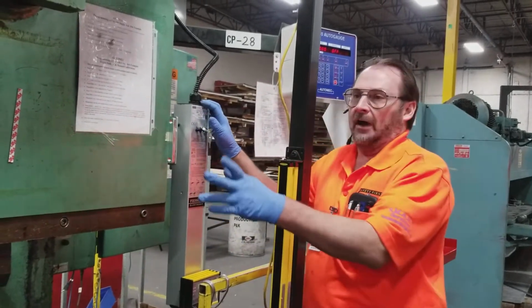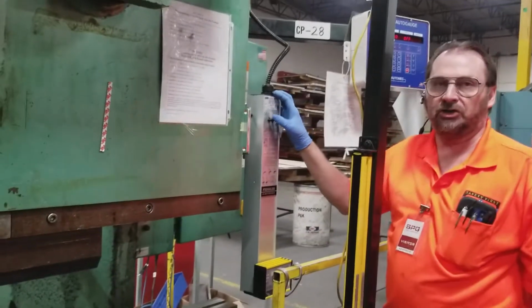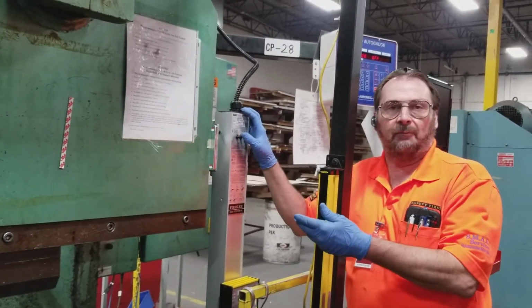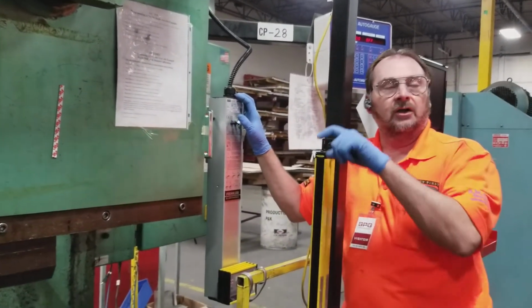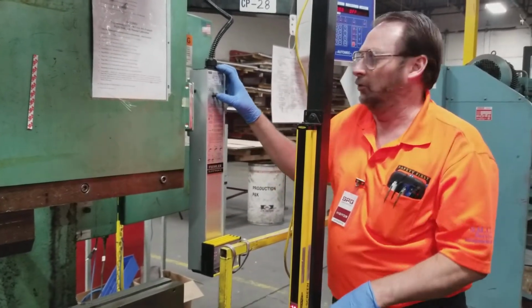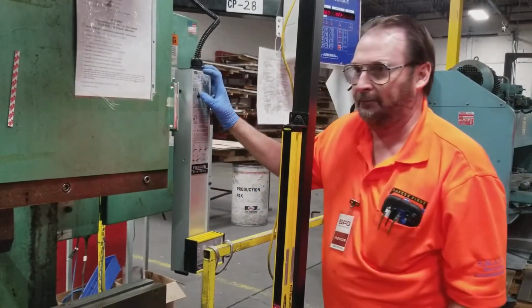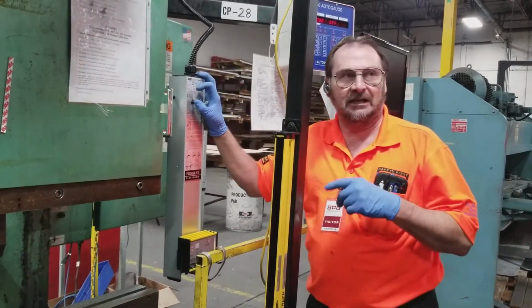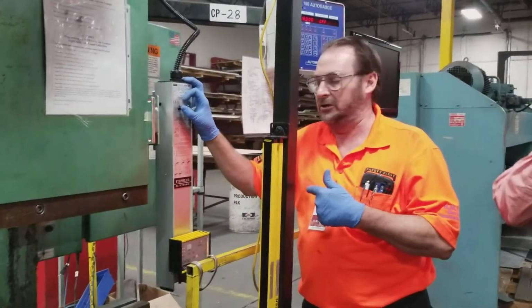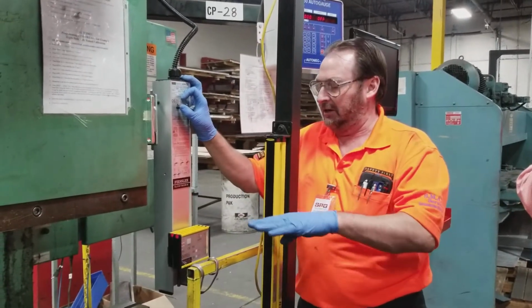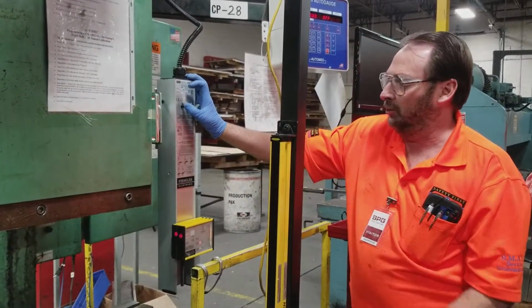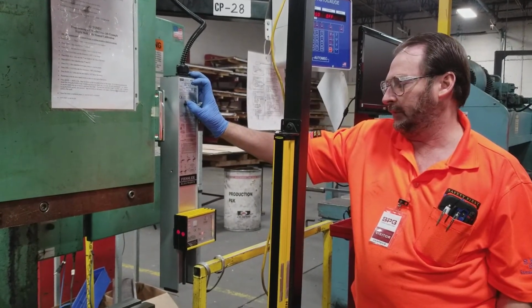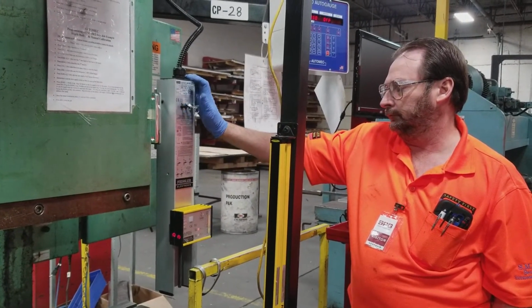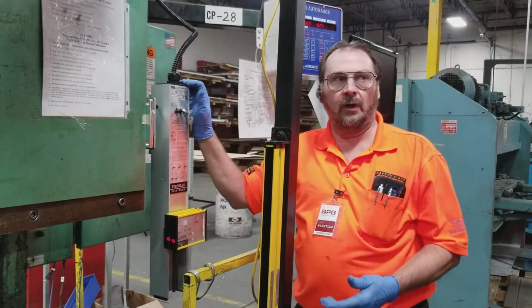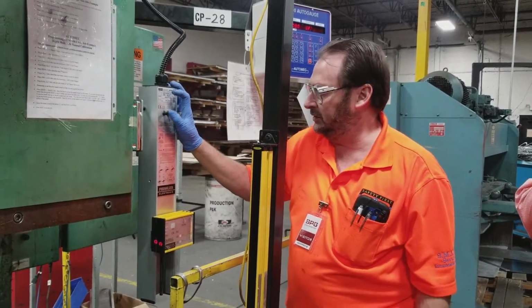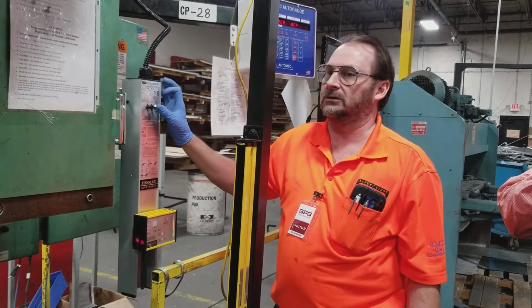Okay, now we've got our transmitter in place. We can push and hold the black button to bring the receiver up. If we push and release the black button, the receiver automatically goes downward. So we'll push and hold it, bringing the receiver up until it comes up and sees the transmitter. Once the transmitter and receiver see each other, it will hesitate. When it hesitates, that's when we release the black button. At which point, now we're ready for calibration. Push release, toggle up release, turn the key off.